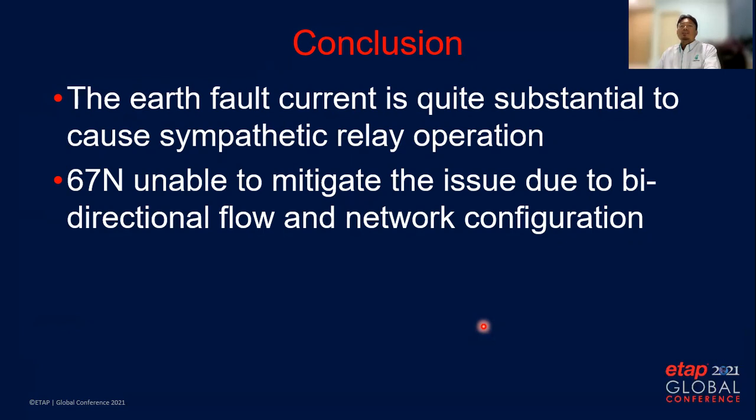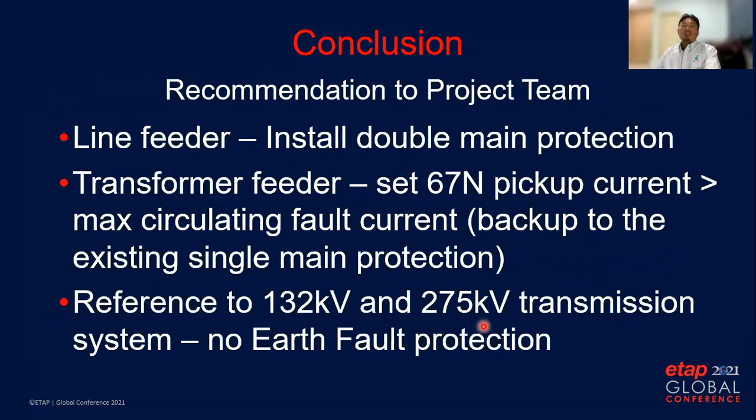Some consultants say that the directional relay is able to mitigate this issue, but from our analysis we recommend the project team adopt the following: Number one, install double main differential protection, because the original design only has one differential protection. This practice is normally used in transmission networks for a reliable protection system to clear faults. Number two, while waiting for installation of the double main protection, only enable directional earth fault protection for transformer feeders with pickup current higher than the simulated circulating fault current. This 67N will serve as backup for the single main protection.